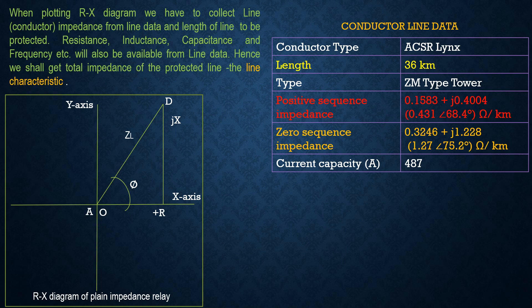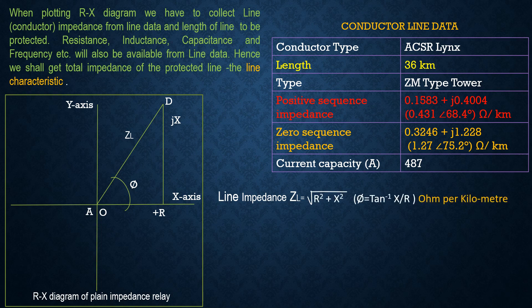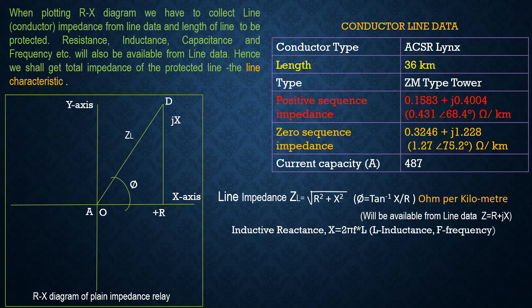The positive sequence impedance is 0.1583 + j0.4004, that is 0.431 Ω/km at an angle of 68.4 degrees. The resistance of the conductor is 0.1583 Ω/km, the reactance is 0.4004 Ω/km, and the calculated impedance is 0.431 Ω/km at an angle of 68.4 degrees. Impedance is calculated using the formula: ZL = √(R² + X²), and angle φ = tan⁻¹(X/R).